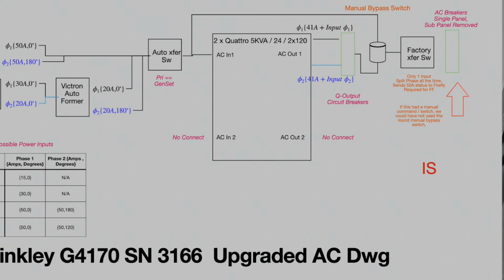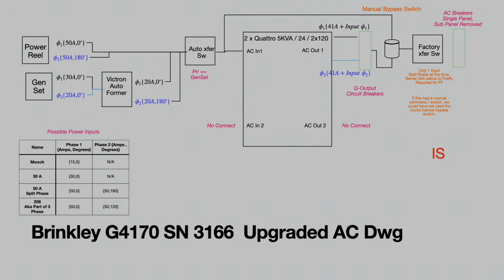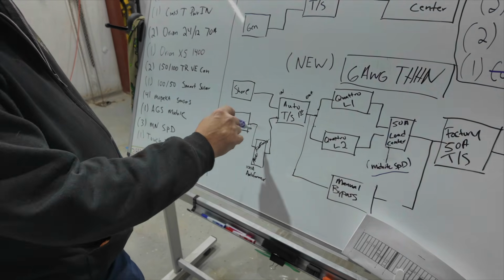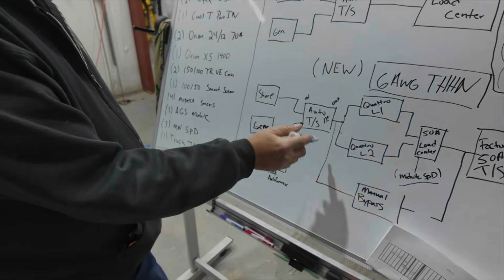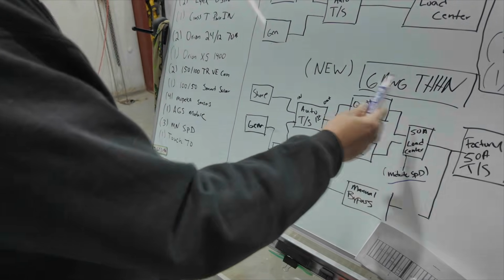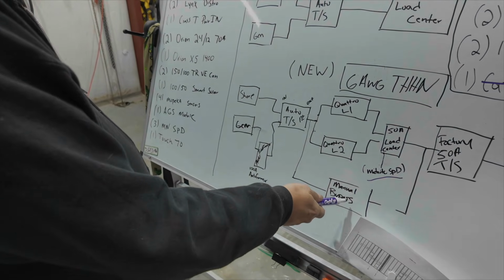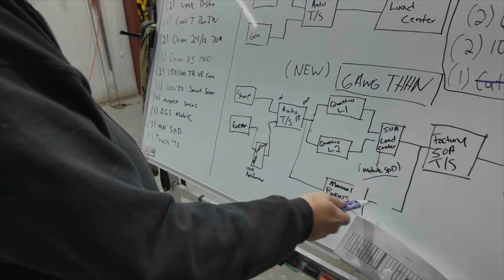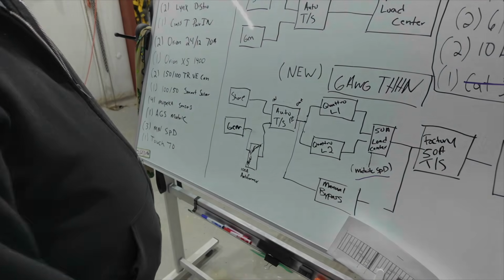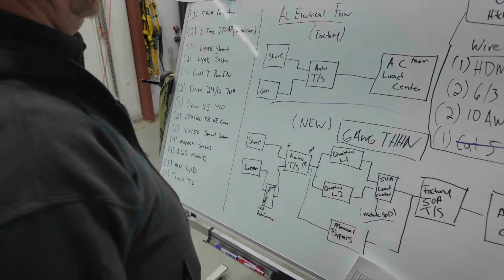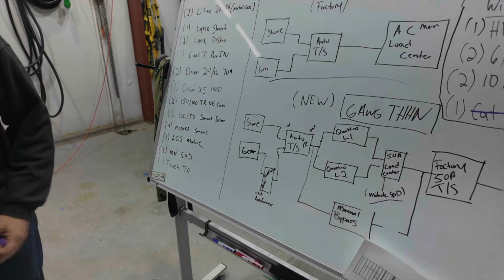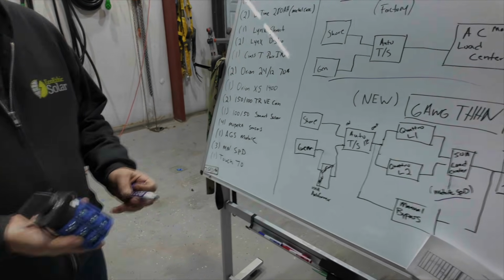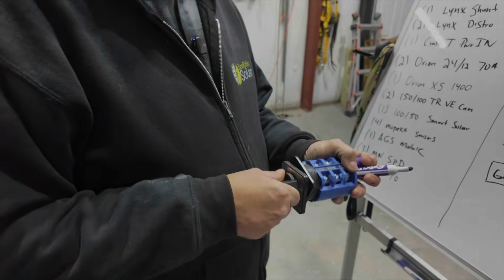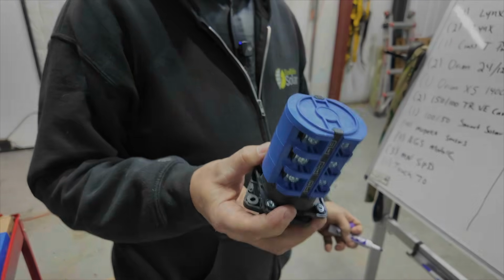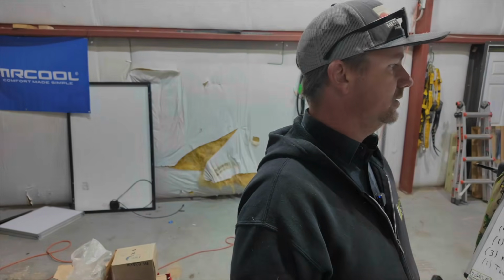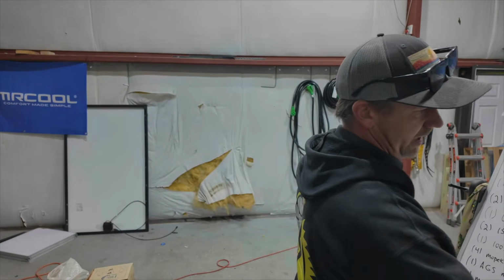And then if you see here, there's a bypass. So what this allows is these two can still come into the first transfer switch, but if you ever have a problem with any of this, you flip the manual bypass, and now you can bypass all of the inverters and still function, as if it's this again. So that's how that works, and that's what these types of switches are for. That's a 50 amp manual transfer switch that will be able to transfer both hot lines and your neutral. So we can just bypass all of that.